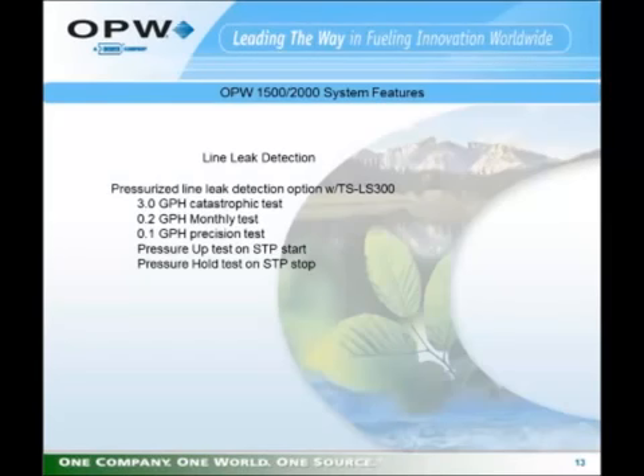For line leak detection, when interfaced with the Incon TS-LS300, both units will perform 5 different tests on a pressurized line leak system: a 3 gallon per hour catastrophic leak test, a 0.2 gallon per hour monthly precision test, a 0.1 gallon per hour annual precision test, a pressure up test when a submersible turbine pump starts, and a pressure hold test when a submerged turbine pump stops.